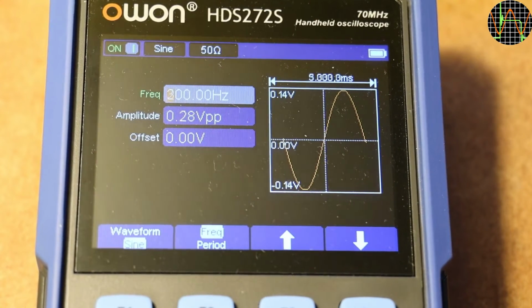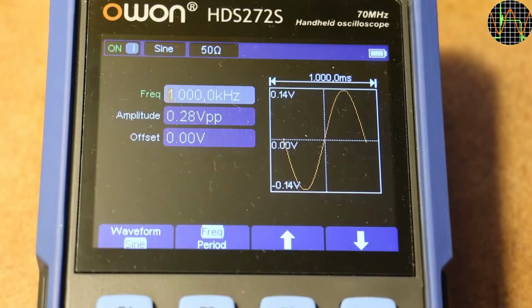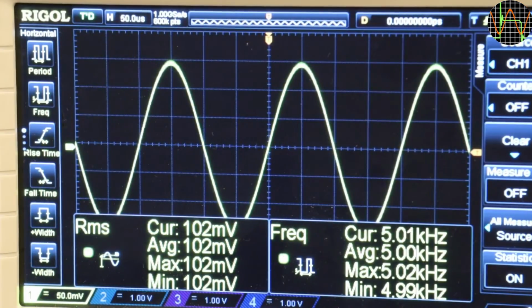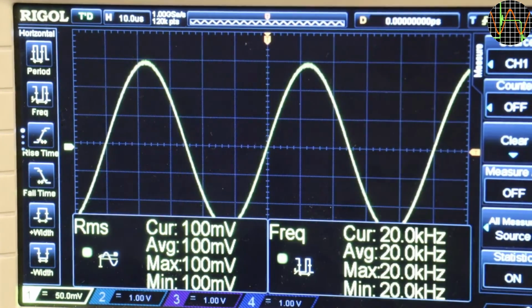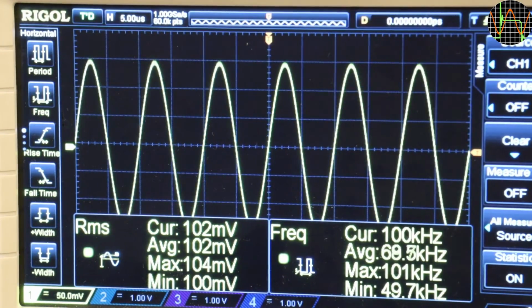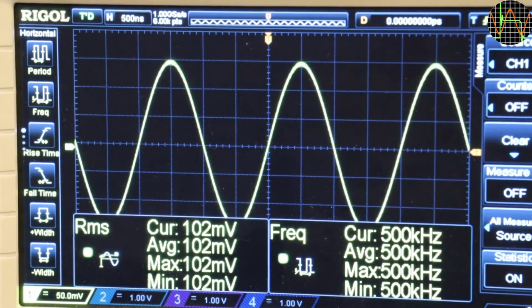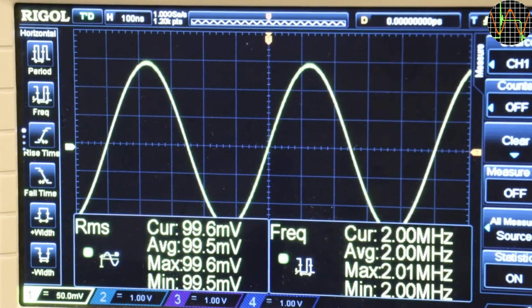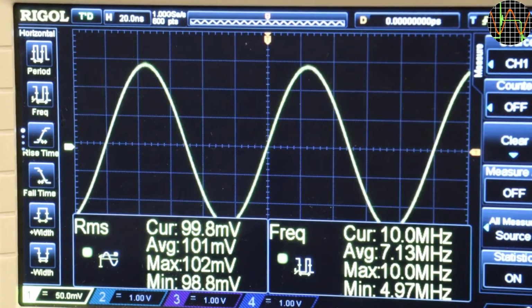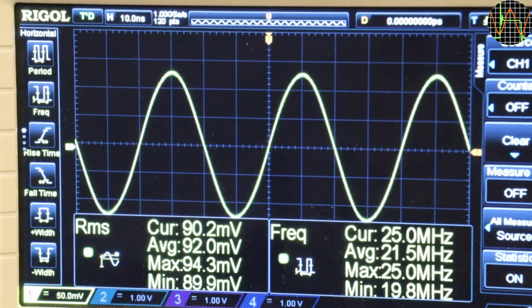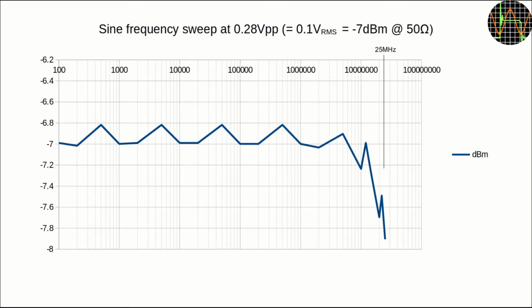The next question is, how stable is the amplitude over the frequency range? To know this is important if you want to use a generator for testing frequency range of multimeters or amplifiers. I'm using my Rigol scope to verify the output voltage of the HDS272S generator because it's the only thing I currently have that can measure AC voltages across this frequency range. Again, OWON does not specify anything on how stable the amplitude is supposed to be, but the results are actually quite good. The generator is very stable. It only starts to drop beyond 10 MHz, but the drop is still less than 1 dBm all the way to 25 MHz.